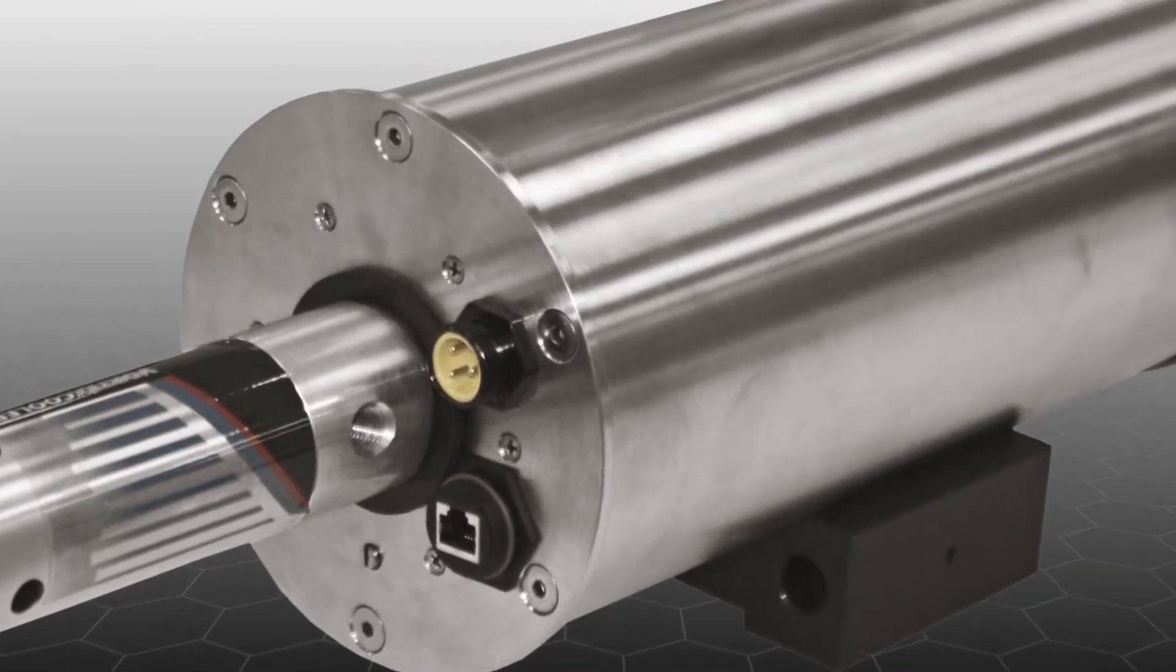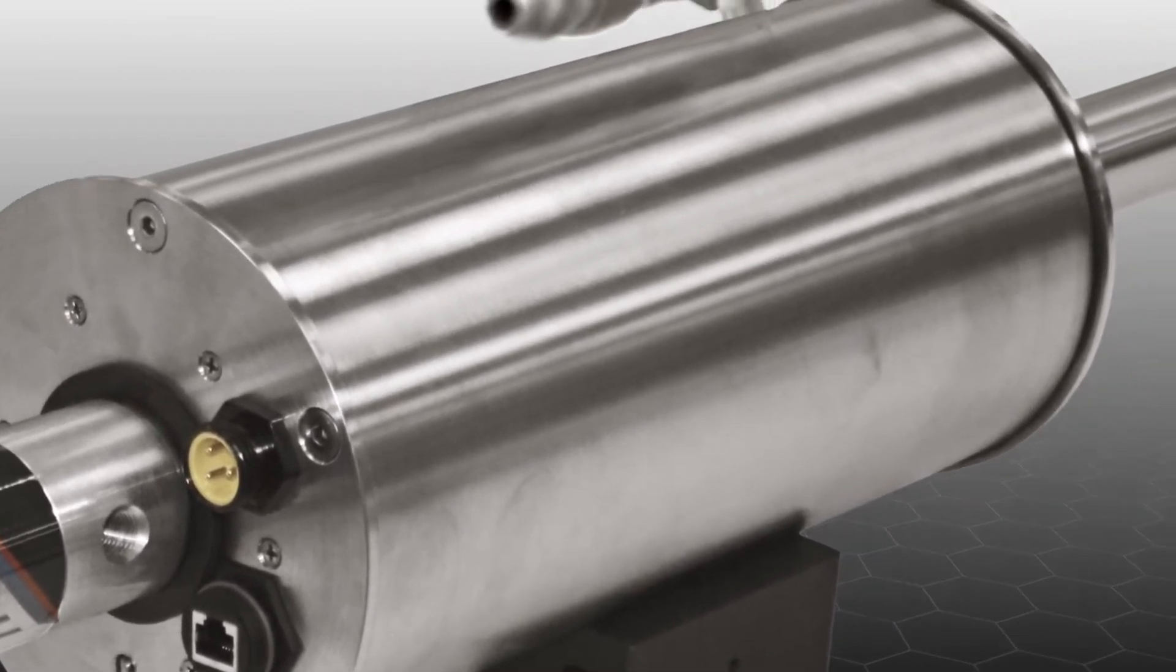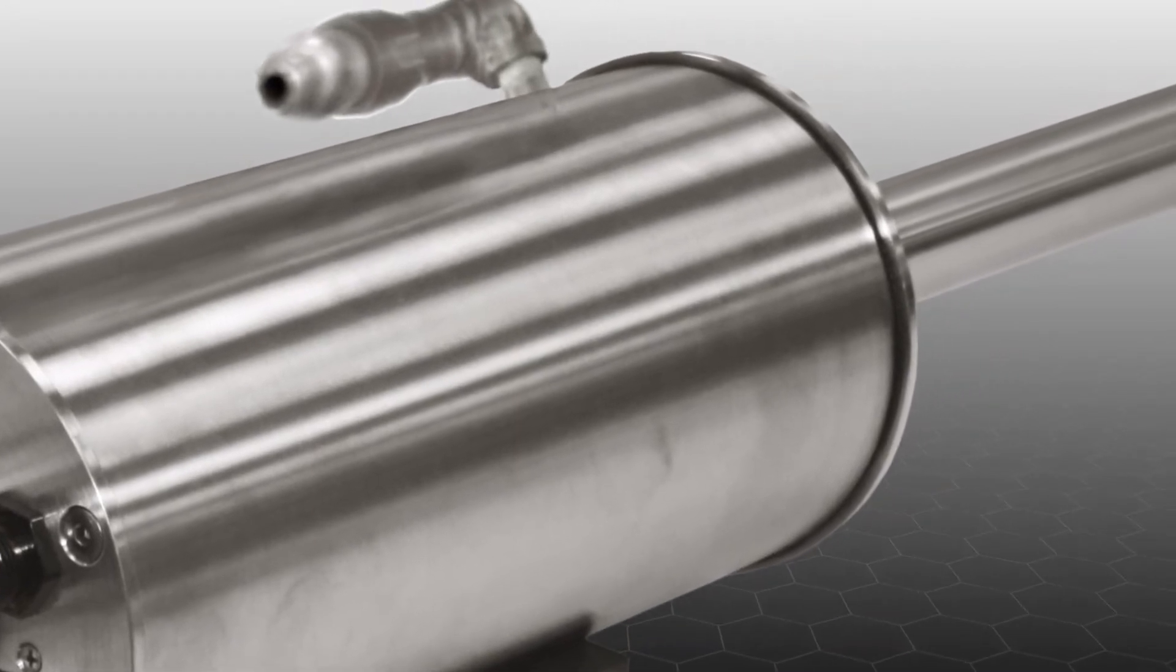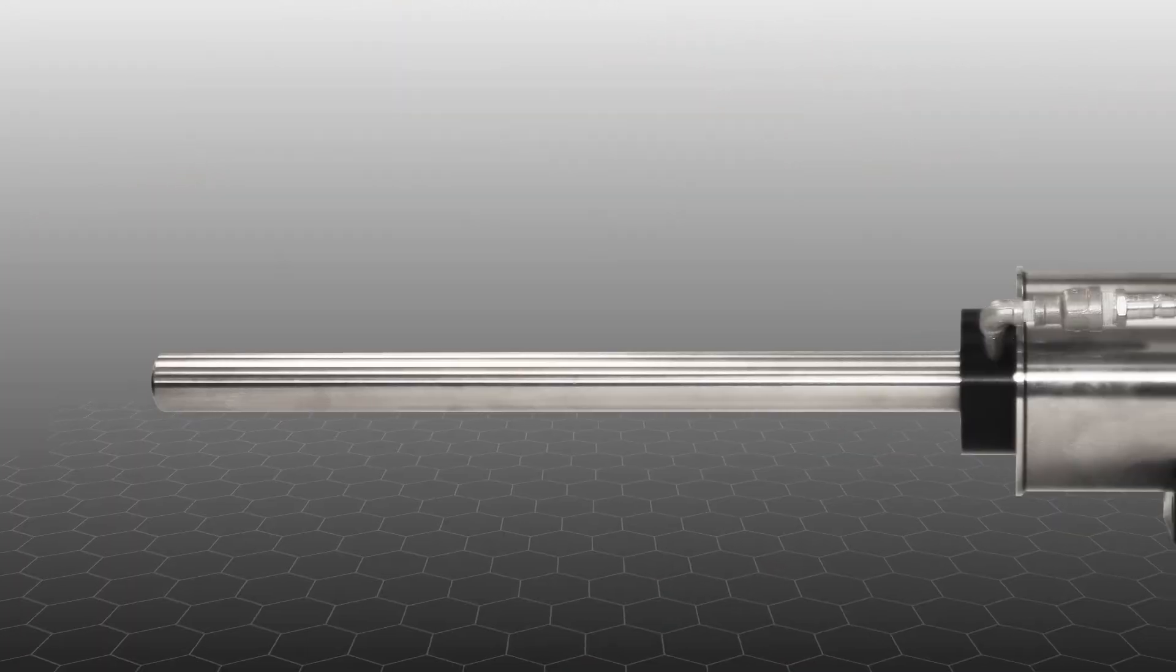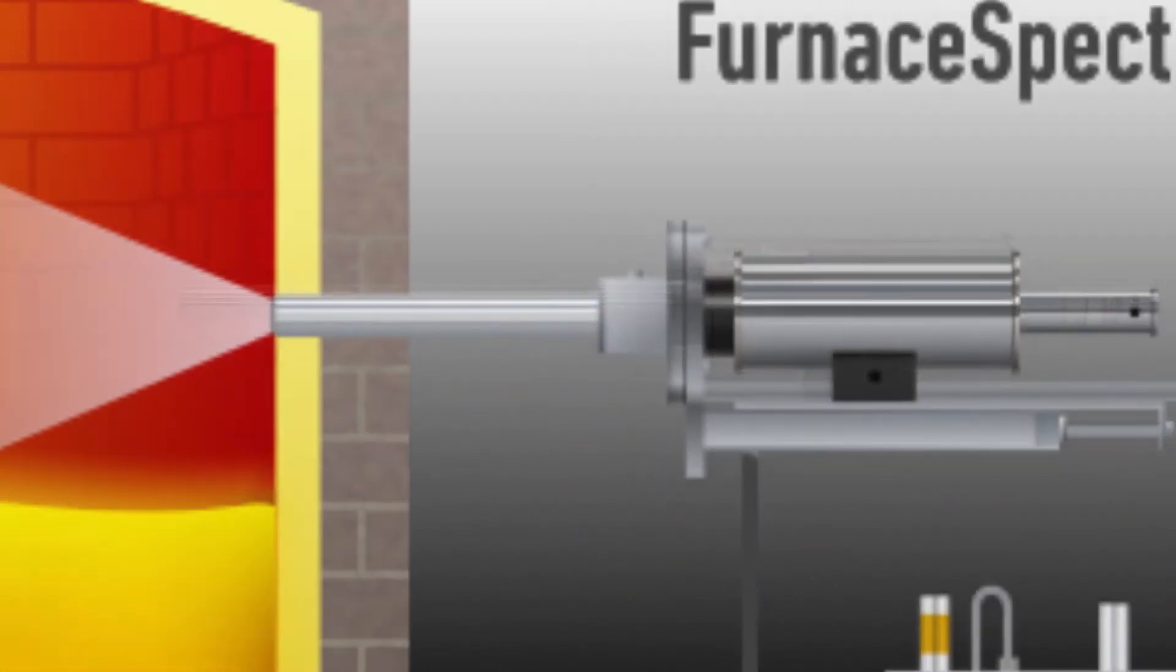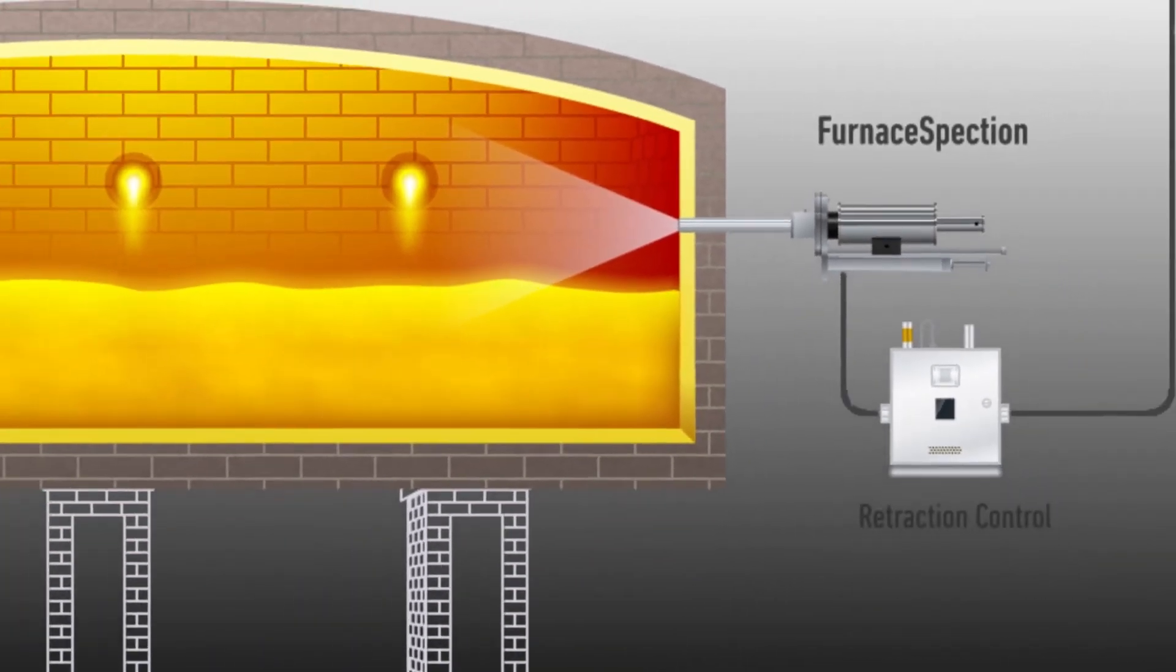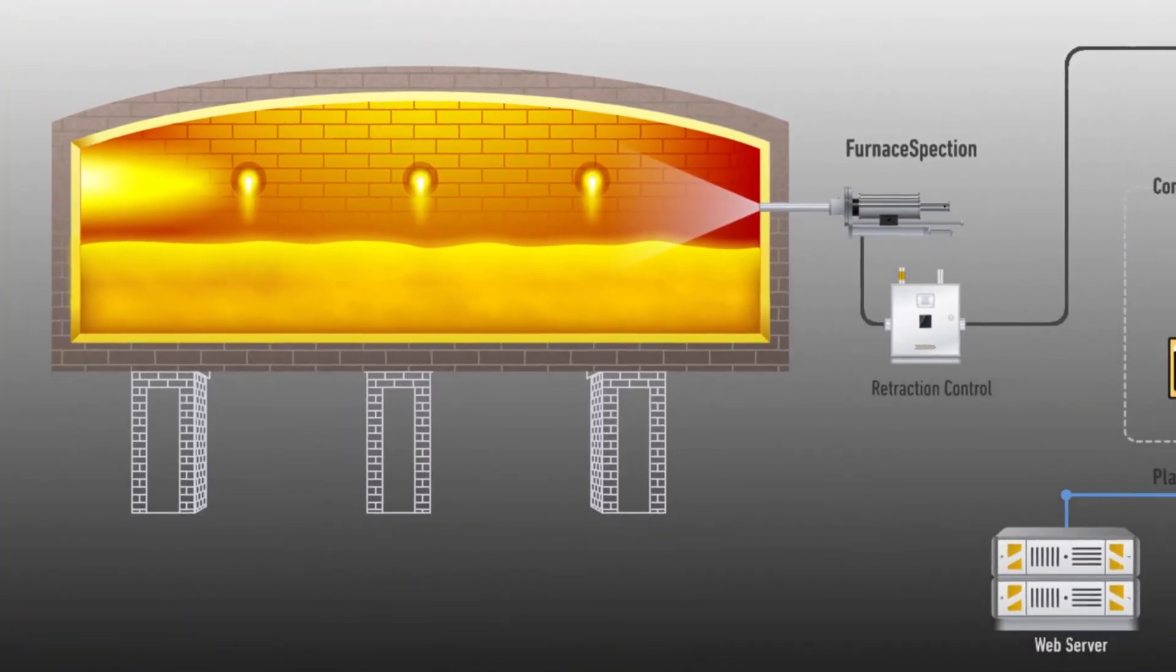An industrial protective enclosure that can be cooled using pressurized air or water allowing the camera to withstand the high heat, and a retraction system that will automatically withdraw the camera from the furnace if there is a loss of compressed air or power preventing it from being damaged.